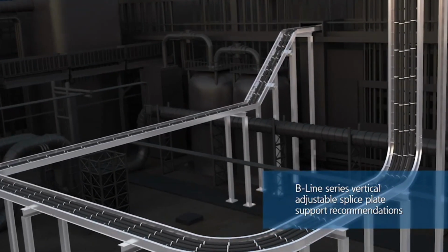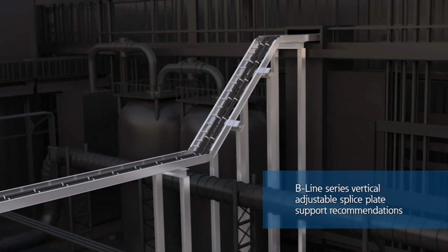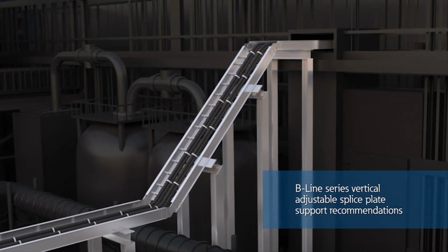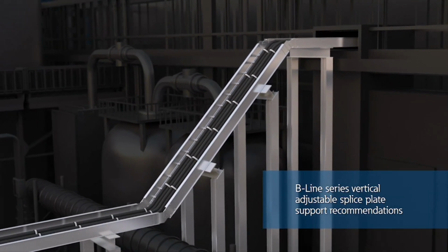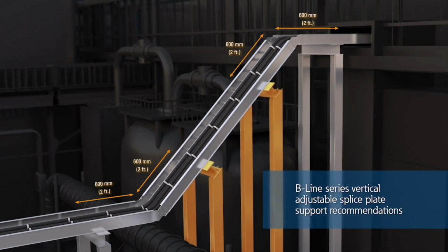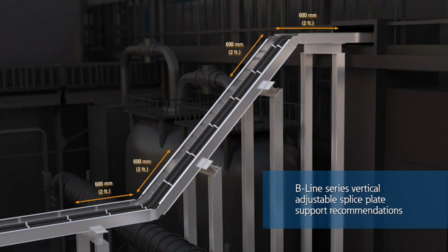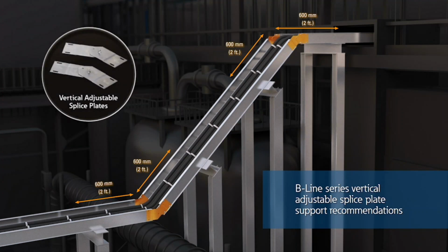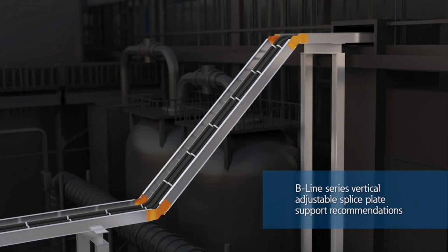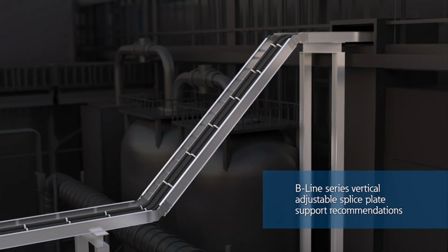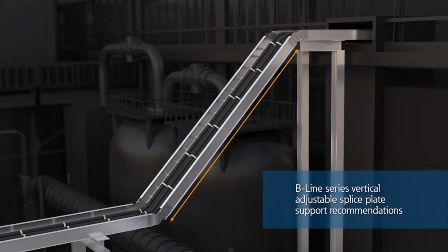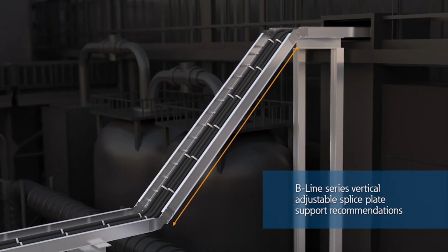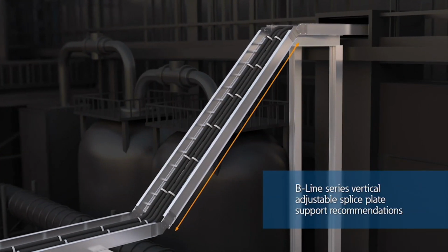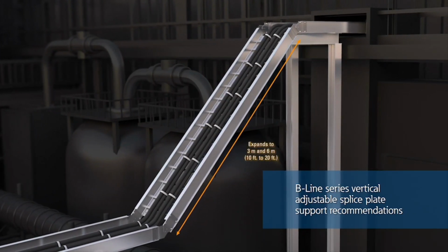Next, let's review how Eaton splice plates and engineered I-beam provide proper support and superior flexibility throughout the system. NEMA VE2 recommends to support the adjustable splice locations within 600 millimeters of each splice location. With Eaton's B-Line series vertical adjustable splice plates, managing elevation transitions is simplified by eliminating supports on the inclined section of cable ladder. The vertical adjustable splice plates are designed to maintain the maximum load classification of the series of cable ladder utilized across the unsupported spans. Depending on the series utilized, incline spans between vertical adjustable splices can range from 3 meters up to 6 meters.